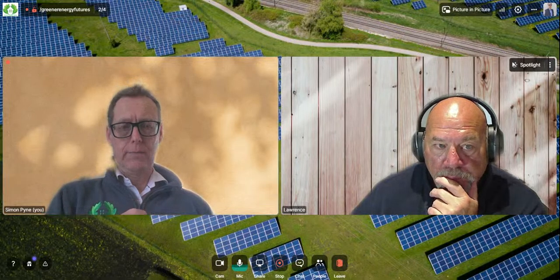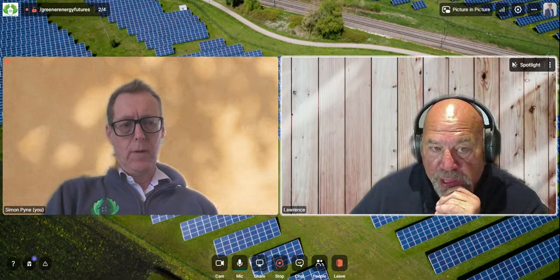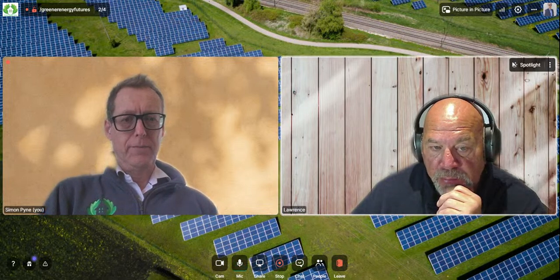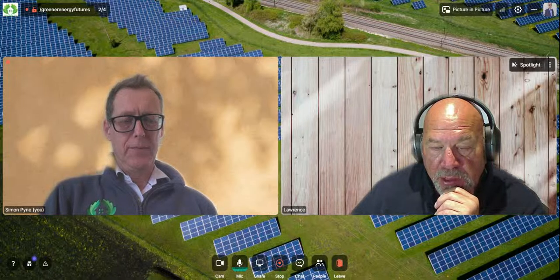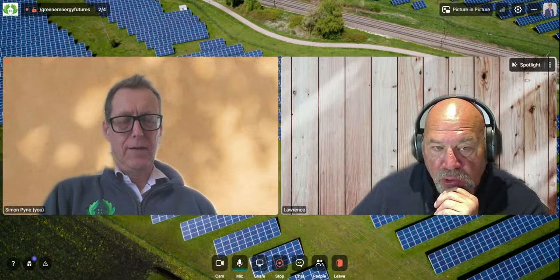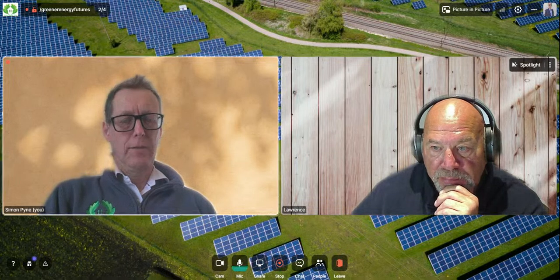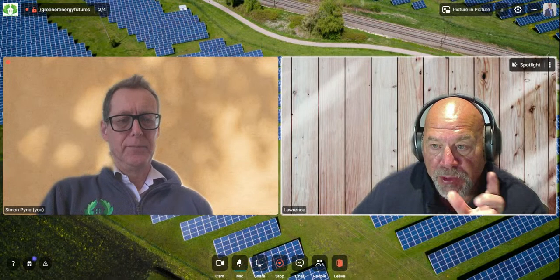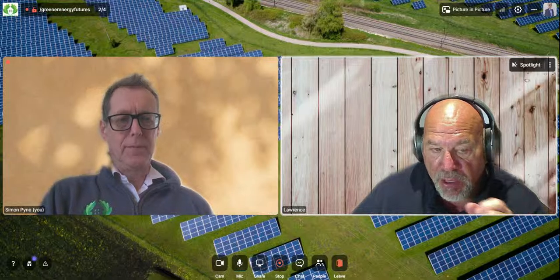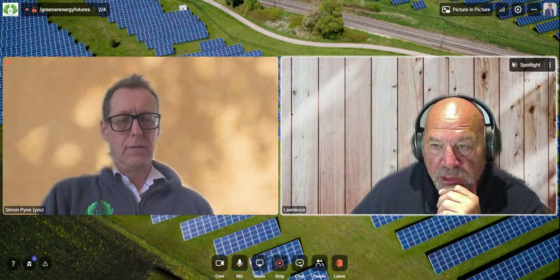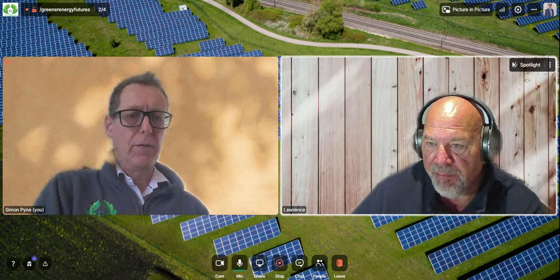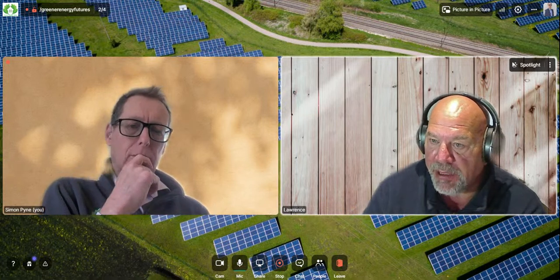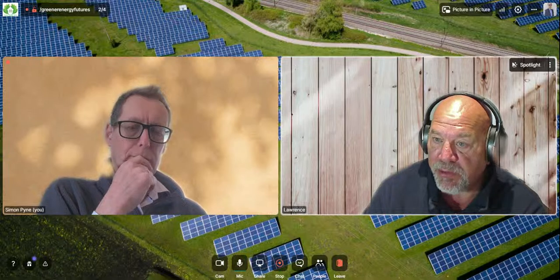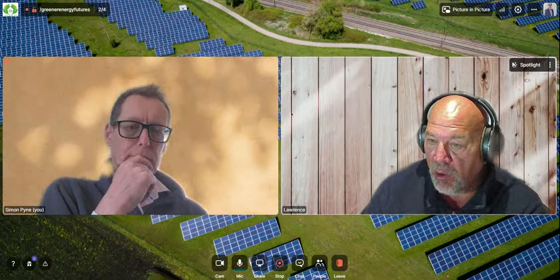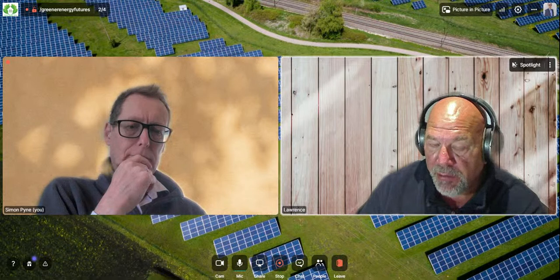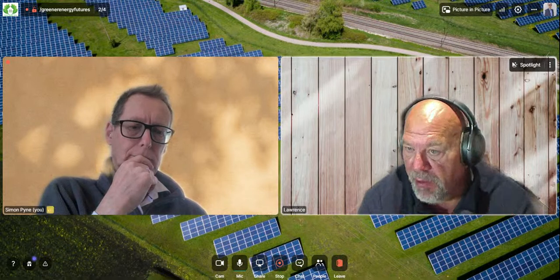Anything you'd like to add? Yeah, this is a really good tip, from work I did with one of my big food companies. Go around your site and record every motor, its rated size - that's the kilowatts off the side of the plate. Look at how that motor - I'm really looking about pumps and fans here, so air handling units, or pumps for hot water or domestic cold water, building services. Record every single pump of a size.